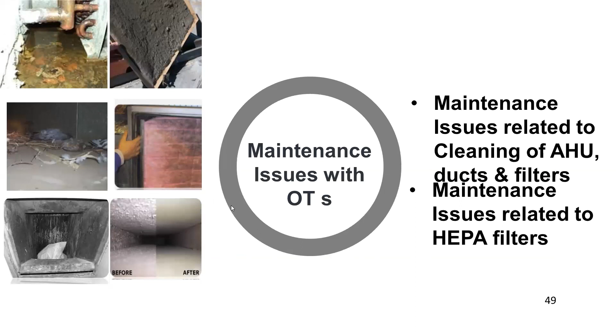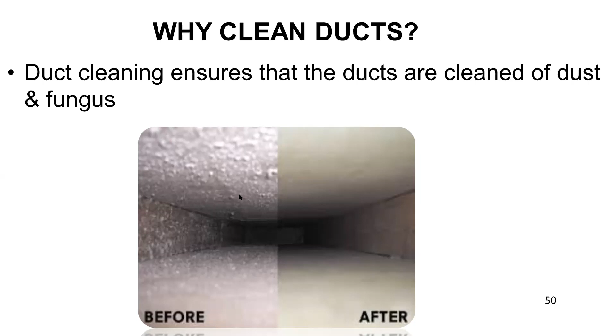So we are going to talk of why we have to clean the ducts. If you have had the chance to see any duct inside, not only in healthcare facility, even in your commercial facilities, you'll find that these ducts are where there is a residence of all this dust and fungus. Same is the case with operation theaters and other healthcare places. And we are talking of super clean areas down there, and the duct itself can be quite contaminated. So it is a good practice to have this duct cleaning, which ensures that the ducts are cleaned of dust and the fungus.